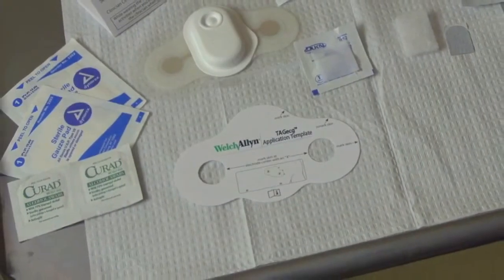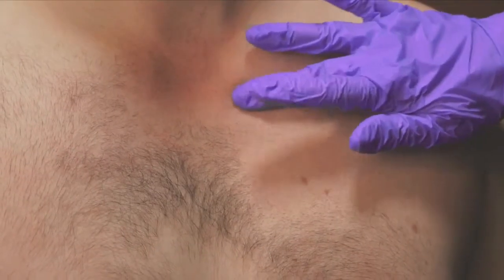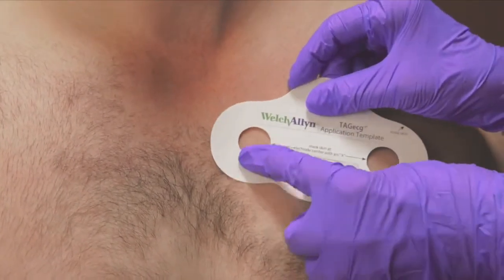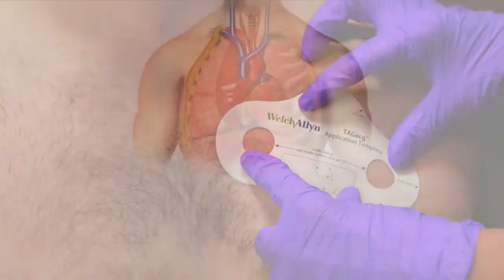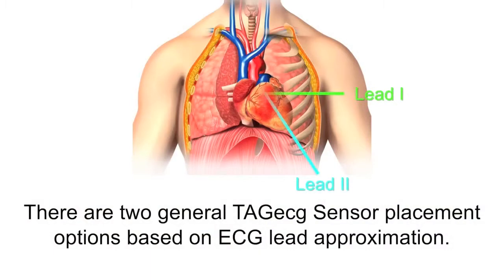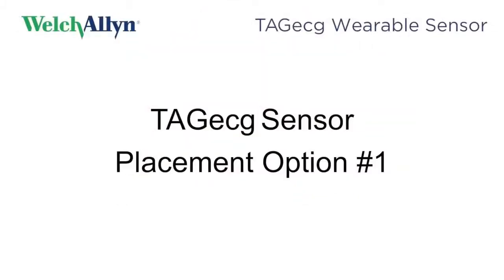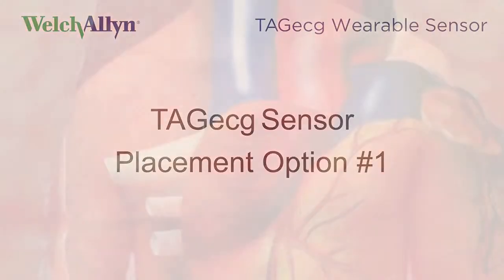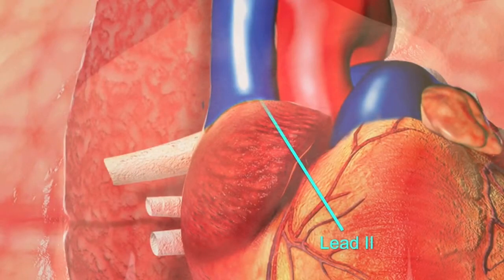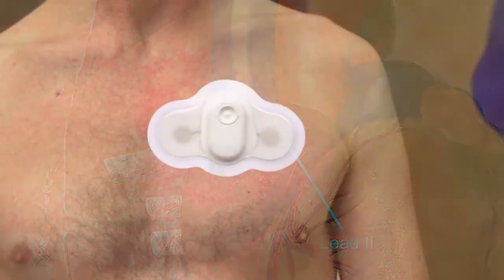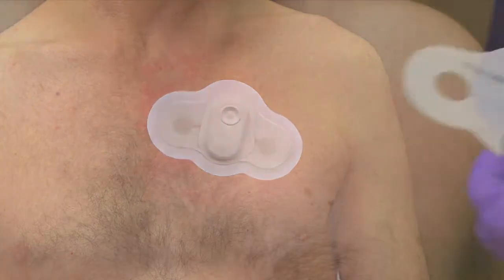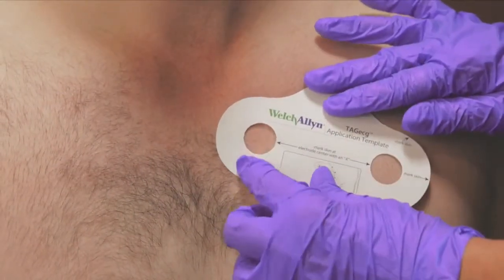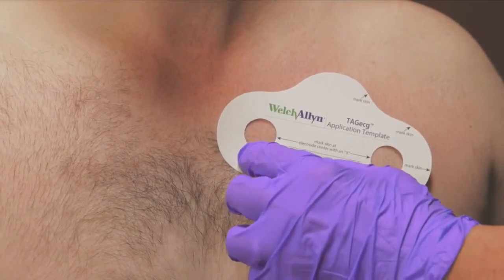Application template. Before you prepare the skin, use the provided application template to estimate the sensor placement area on the patient's left chest and consider the following placement alternatives. There are 2 general TAGecg sensor placement options based on ECG lead approximation. Placement option 1 approximates the lead orientation of lead 2 of a standard 12-lead electrocardiogram. In this orientation, the sensor is placed diagonally and is the preferred position. For option 1, place the right electrode at the second intercostal space next to the sternum, and the left electrode at the third or fourth intercostal space.